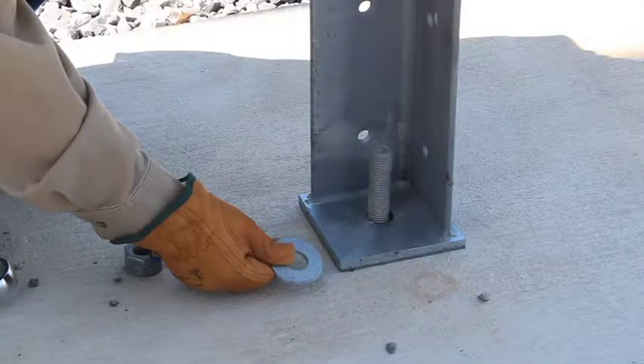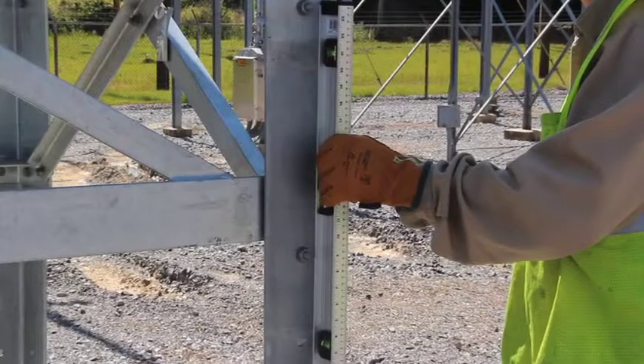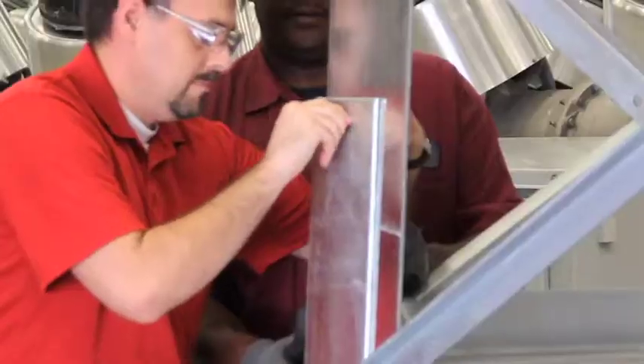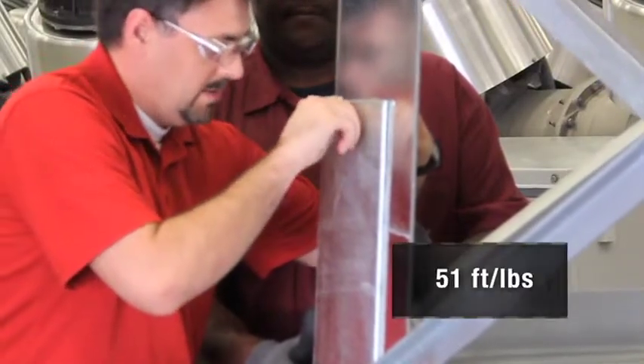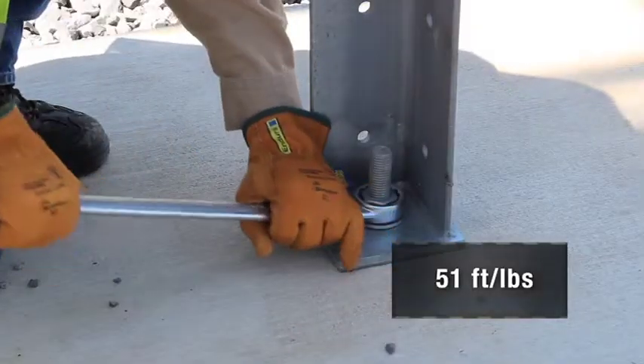The circuit breaker should be level so that moving parts within the breaker can operate freely. When the breaker and legs are properly aligned and leveled, tighten the leg bolts to 51 foot-pounds and the foundation bolts to 400 foot-pounds.